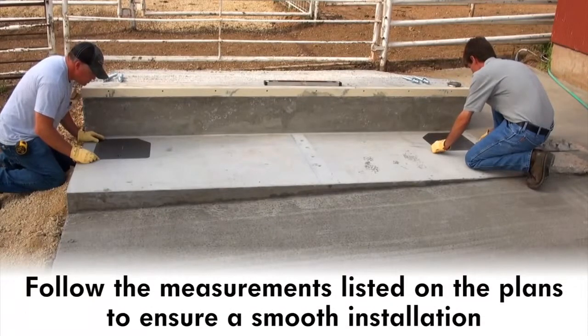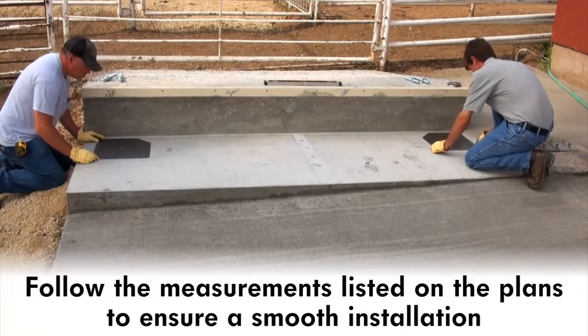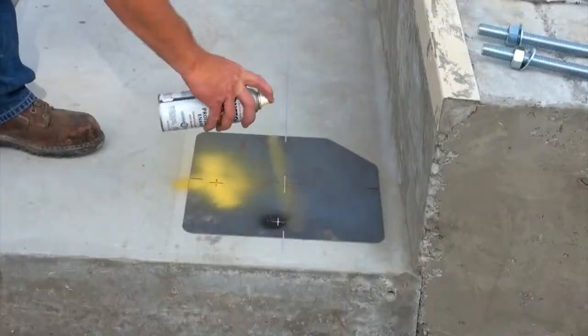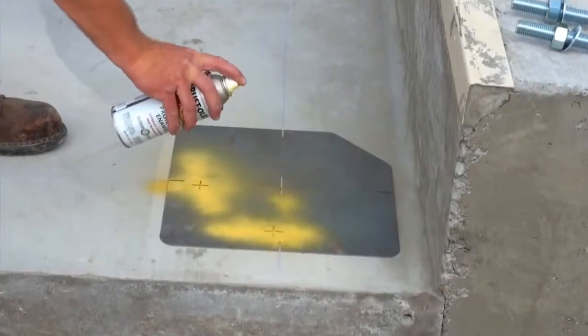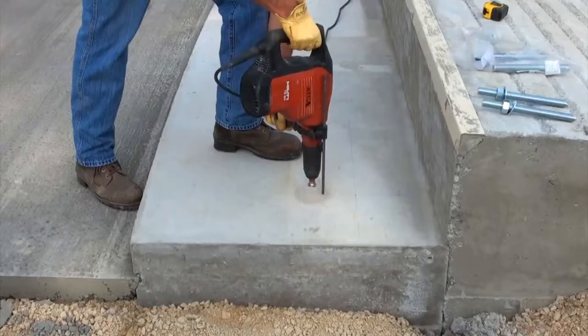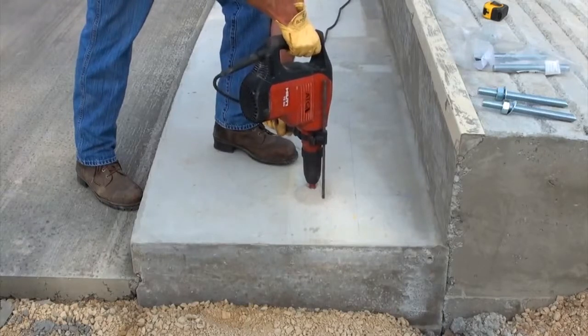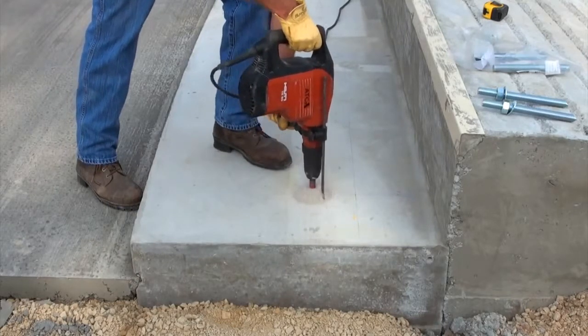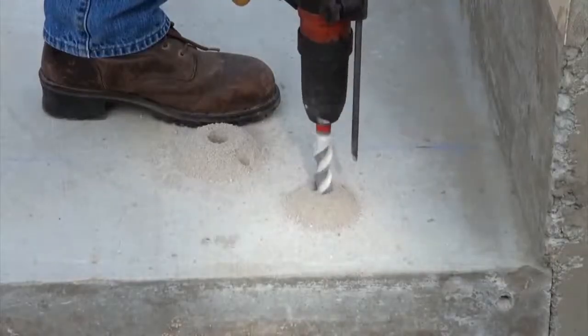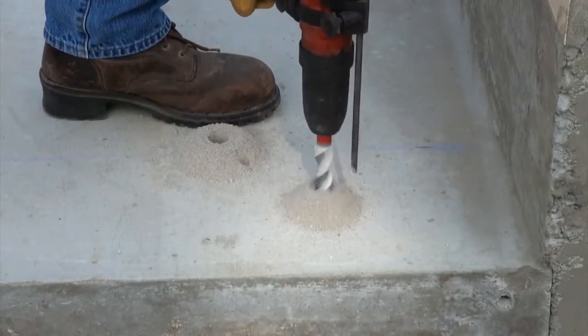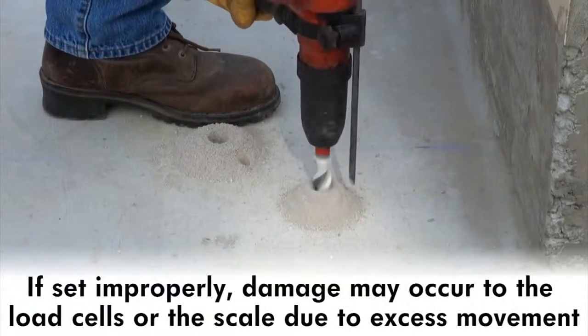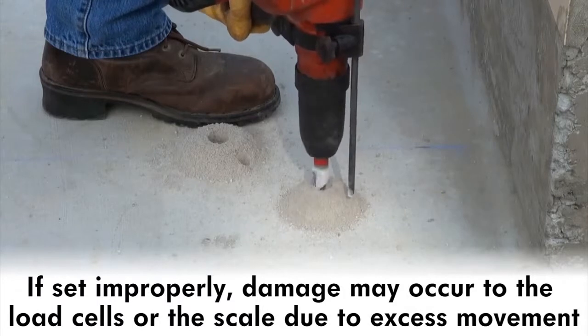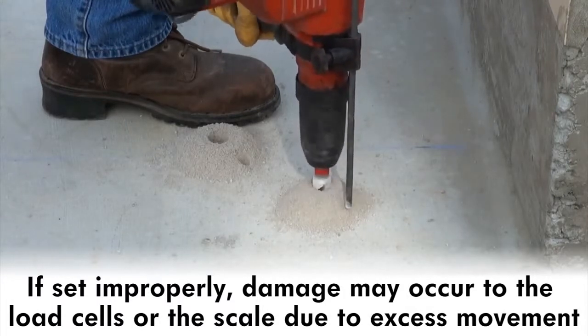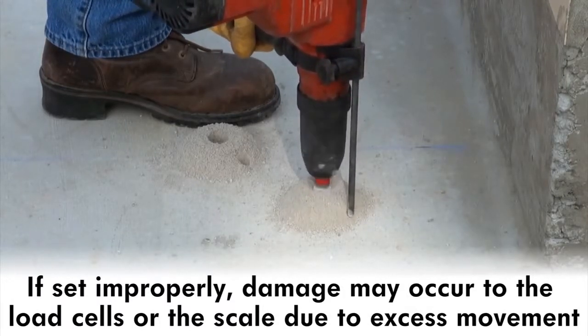Follow the measurements listed on the accompanying plans to ensure a smooth installation. Use the templates to mark where the load cell stands will be located. The load cell stands are not to be grouted in place, so you'll have to drill the holes for the anchor bolts. They should set on smooth and level concrete with preset anchor bolts. Should they be set improperly, damage may occur to the load cells or the scale due to excessive movement.